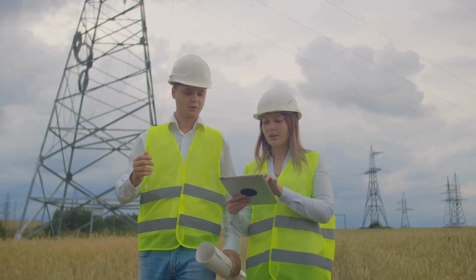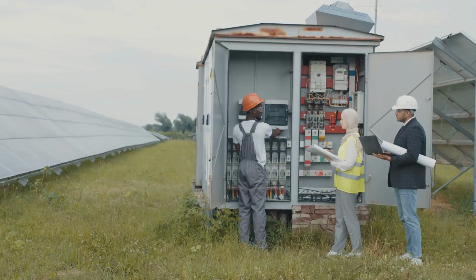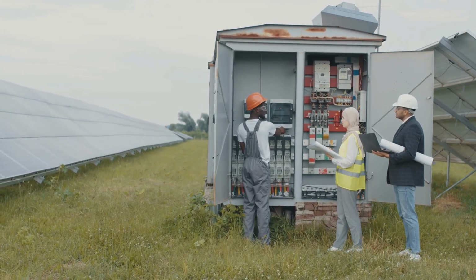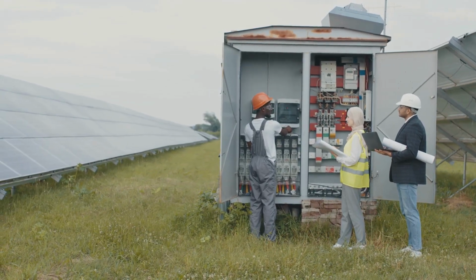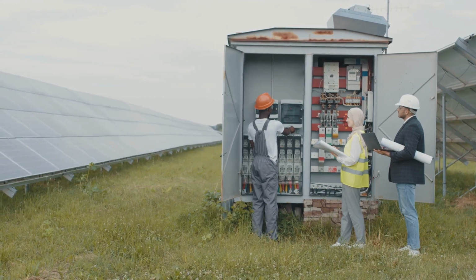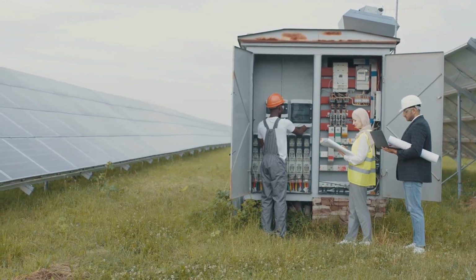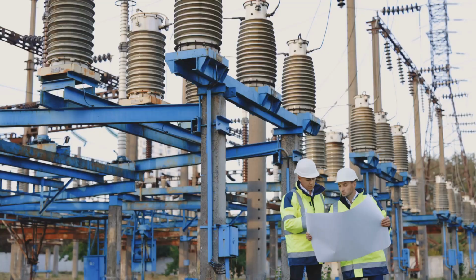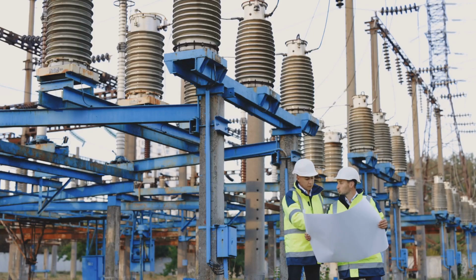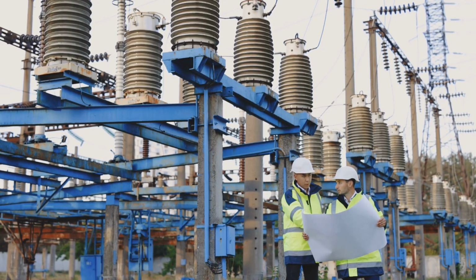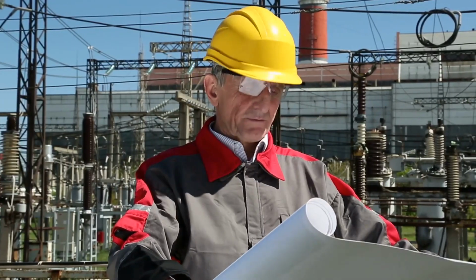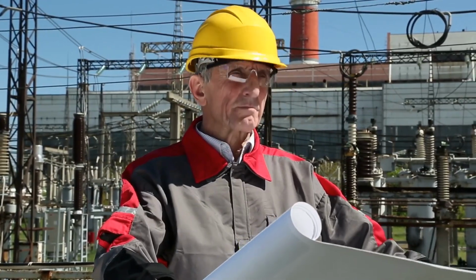DERs must ride through faults but not ride through into an island. That's where advanced anti-islanding detection comes in, using active impedance shifting, frequency monitoring, and voltage asymmetry detection to differentiate between a grid fault and a true island. Clause 8.2, Trip behavior and coordination with protection devices. The DER must trip in coordination with utility protection schemes but not prematurely.